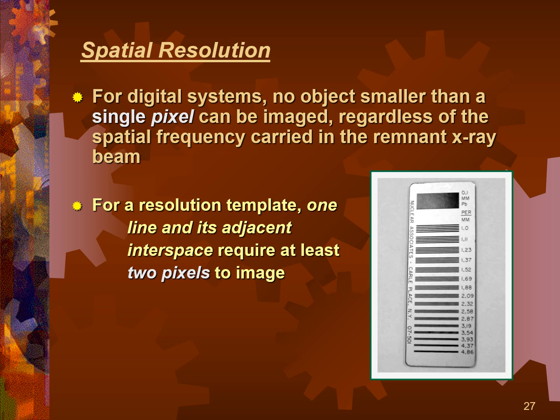And again, my resolution tops out at 1.88. Okay? And the reason is because my pixels are exactly the size of the 1.88 line pair. So it's 1 pixel for the black one, and then the white one immediately below it is the next pixel.